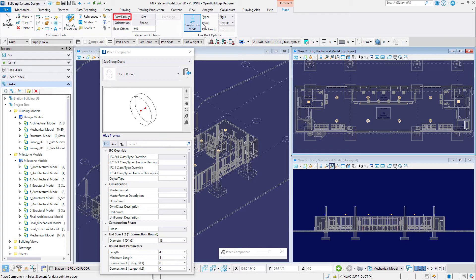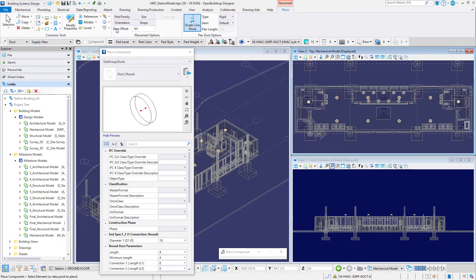You can set the part family option off — when off, the active family and part is assigned to the ductwork. The active family and part for the ductwork should be duct supply new. For this initial ductwork, we will turn off orientation, size, and shape. Basically, you will size the ductwork later using the duct sizing tool.